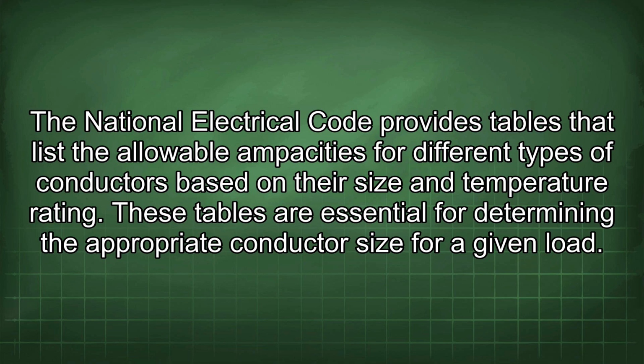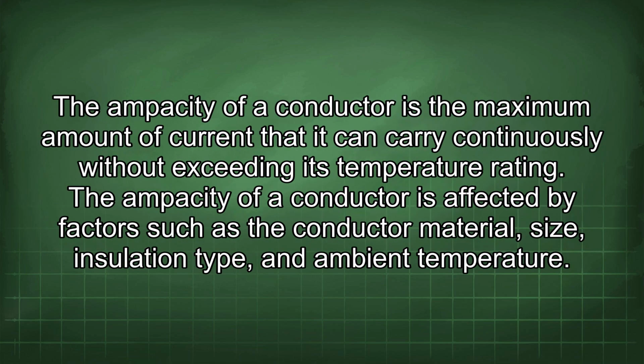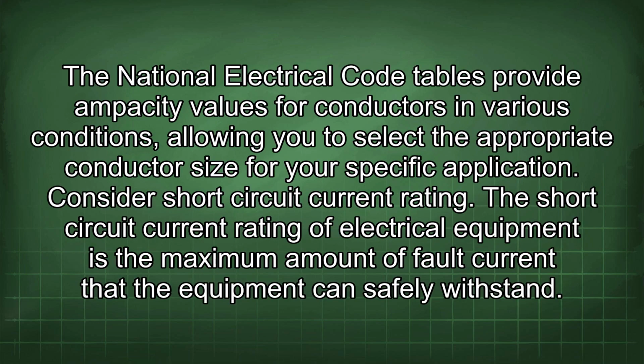These tables are essential for determining the appropriate conductor size for a given load. The ampacity of a conductor is the maximum amount of current that it can carry continuously without exceeding its temperature rating. The ampacity of a conductor is affected by factors such as the conductor material, size, insulation type, and ambient temperature. The National Electrical Code tables provide ampacity values for conductors in various conditions, allowing you to select the appropriate conductor size for your specific application.